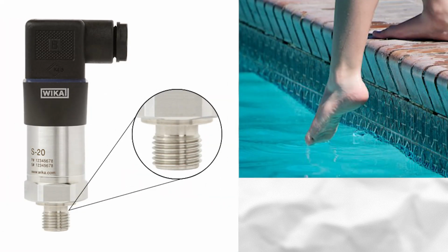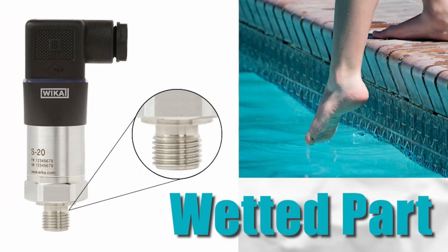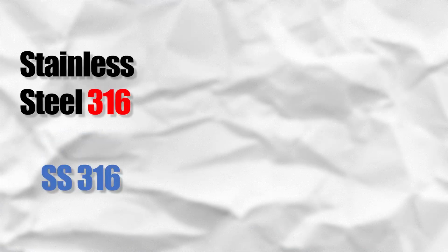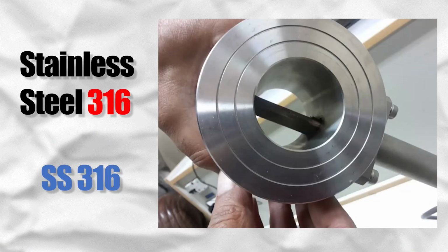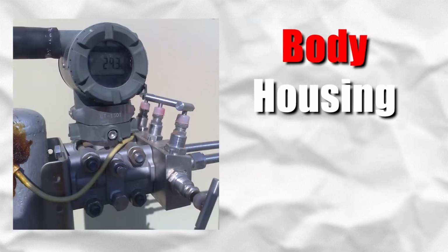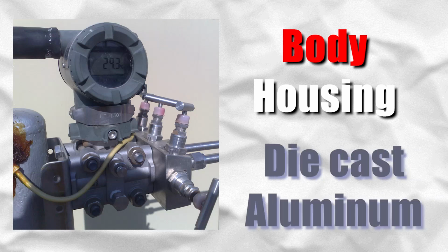Also, an instrument engineer must have enough knowledge to choose the appropriate construction material for a device. I can tell you the part of the instrument exposed to fluid is called the wetted part. The suitable material for this part is considered to be stainless steel 316 as a minimum. The body or housing of the instrument might be die-cast aluminum.